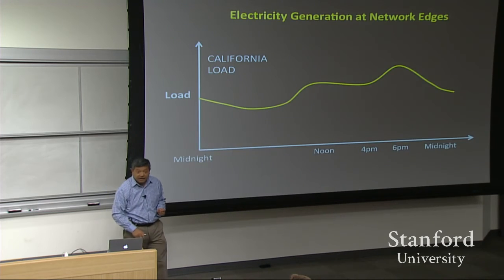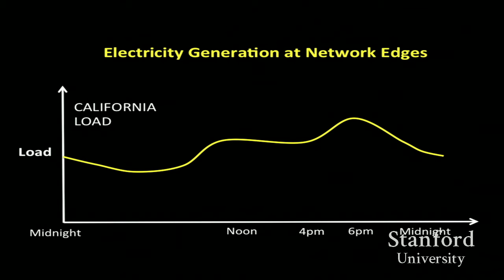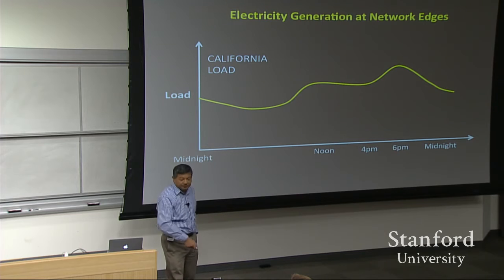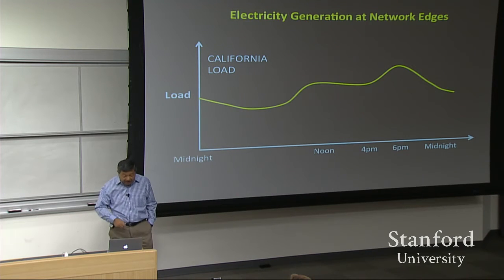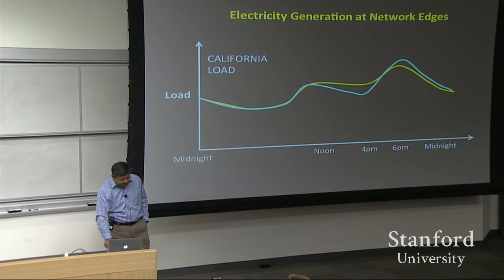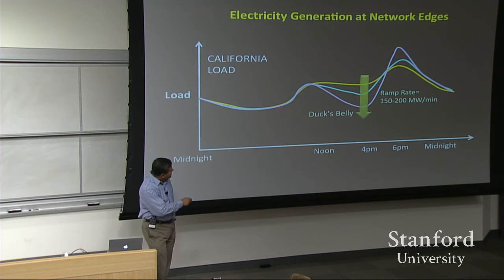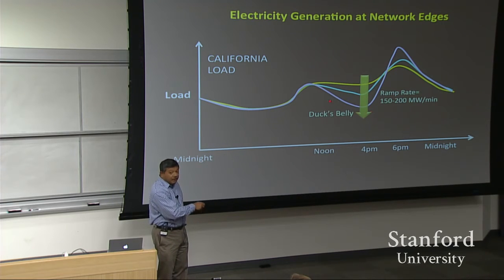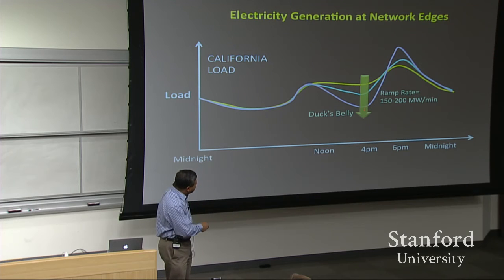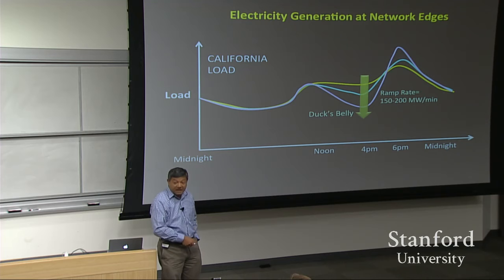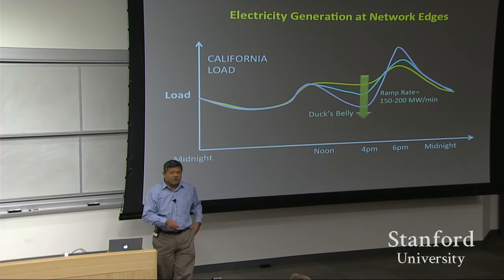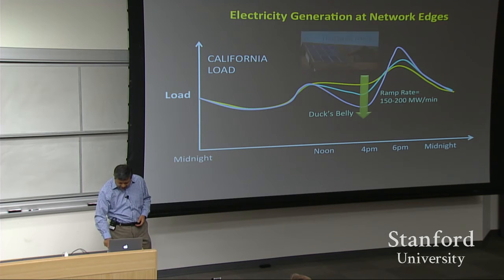This is already happening in California to the extent that it could affect the grid. This is the California load curve, it peaks around noon and then flattens out. When people go home, the load goes up and then comes down again. What is happening today, and will happen more in the future because of what's happening at the edges of the network, is this: the load goes down and then shoots up, to the point that it's called the duck curve, because this is the duck's belly, and the duck is getting fatter. You have a ramp up of about 150 to 200 megawatts a minute between 4 o'clock and 6 o'clock or so. So why is this happening? It's happening because of rooftop solar.